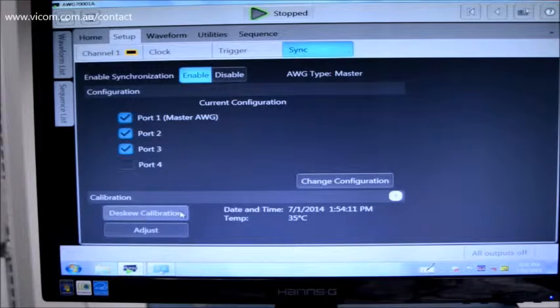Once you've done the calibration though, you should not have to repeat this process, unless you change the configuration drastically. Basically that's the only time you should have to do a Deskew calibration again. Now this Deskew calibration doesn't require an oscilloscope. Basically it just requires the configuration, no connections to the front of the AWG are required, except for going from the output of the AWG into the front panel of the sync hub. And this should be done with the precision cables that are provided with the sync hub.